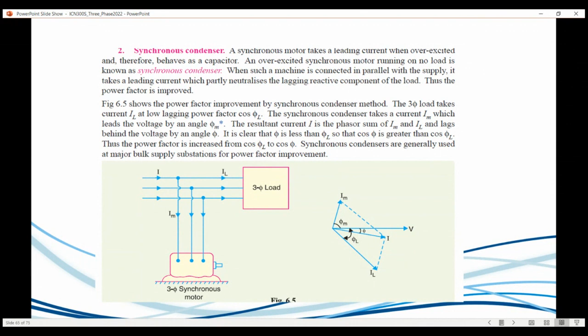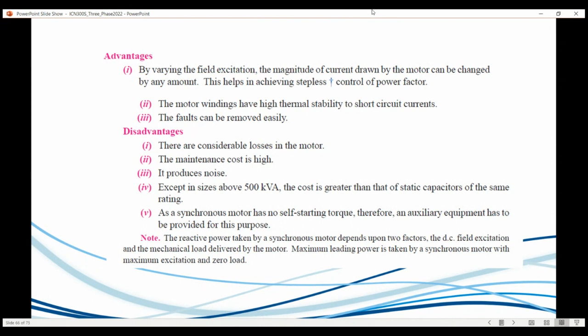This is typically used on a bigger scale, and the synchronous condenser is generally used for major power supply stations. So for a bigger kind of setup, you want to use a synchronous motor to correct the power factor. There are some advantages and disadvantages. I think I'll just talk about the disadvantages. There are losses in the motor, it's high maintenance, and it produces noise. It's a motor, and they're saying that except in sizes above about 500 kVA, the cost is greater. Also, the synchronous motor has no self-starting torque, so you have to provide it. You have to have additional equipment to kickstart it.